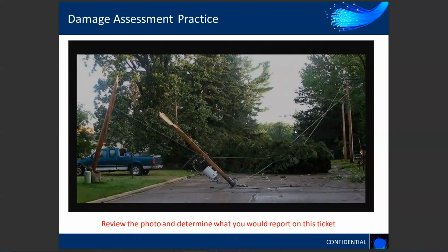Okay. But the truth is, the transformer and wire are probably still good because it's still connected. They probably really just transferred from that pole top to another pole. Just by looking, there's no oil. That transformer hasn't got any oil on the ground, so it's not spilling. The transformer's still working. You've just got to put a fuse cutout because it's going to multiple houses, not one. It's simpler than it looks. Yep, it is. What else would you report on this?